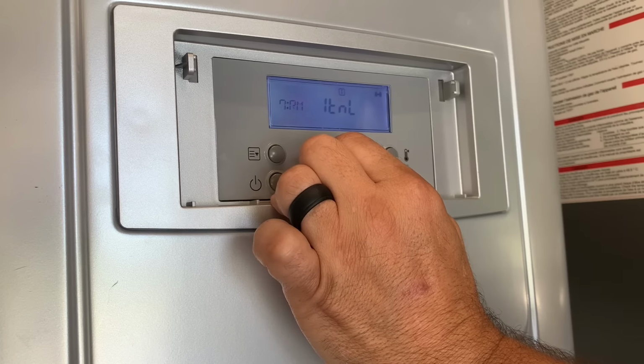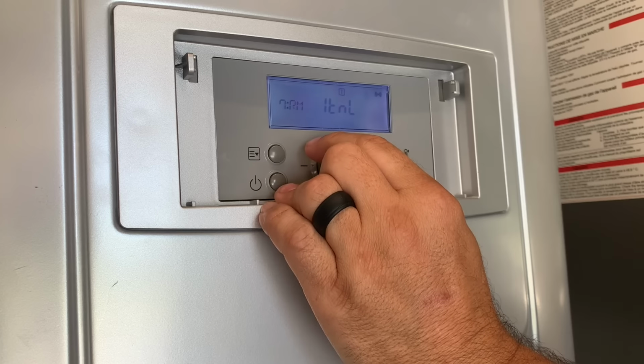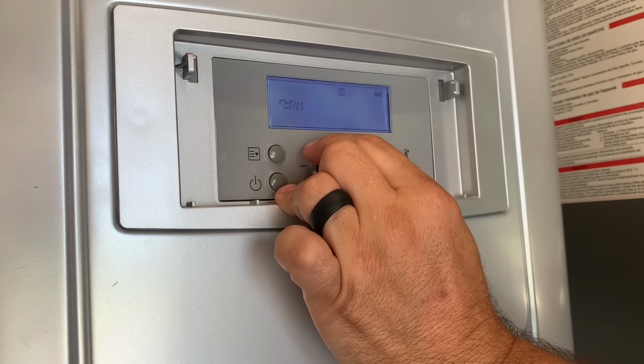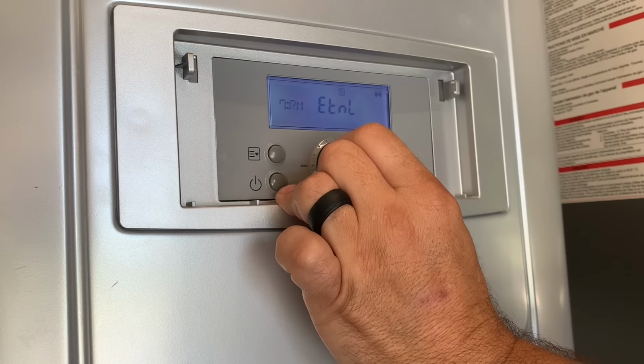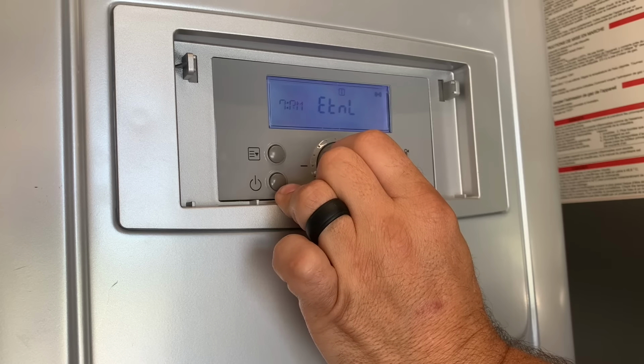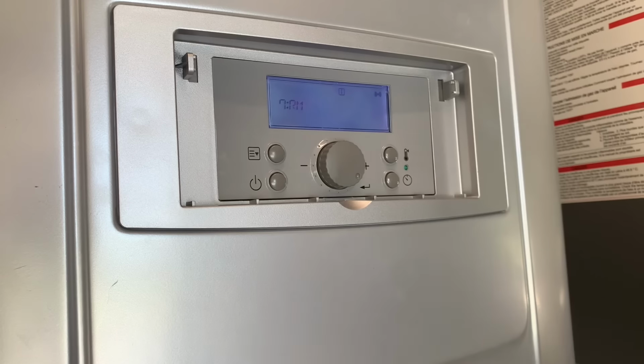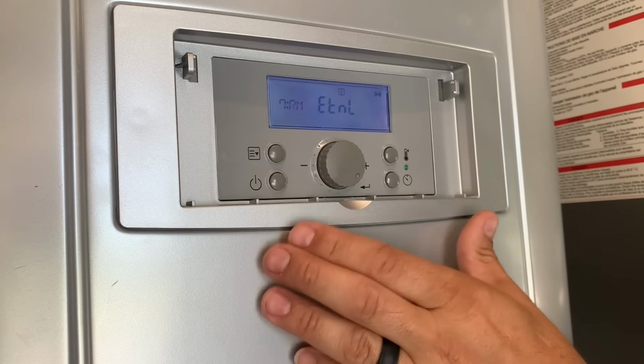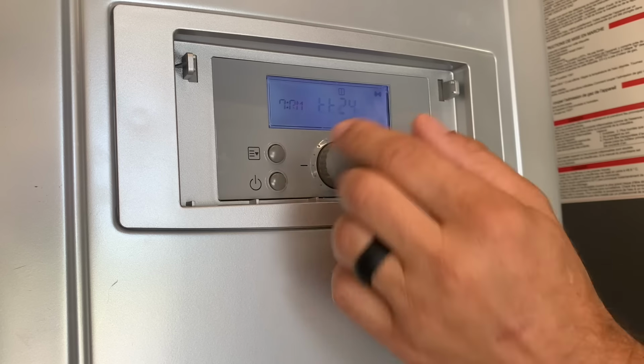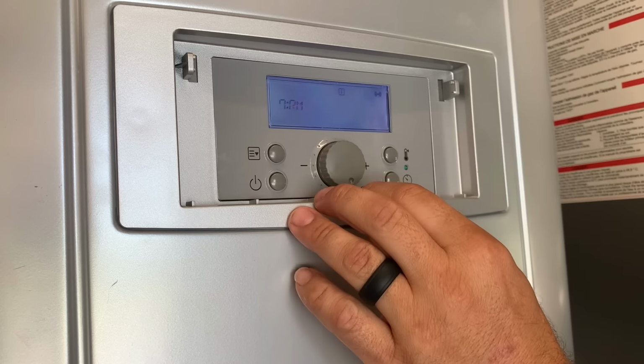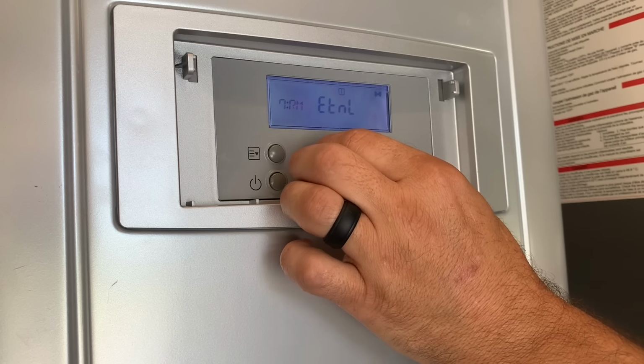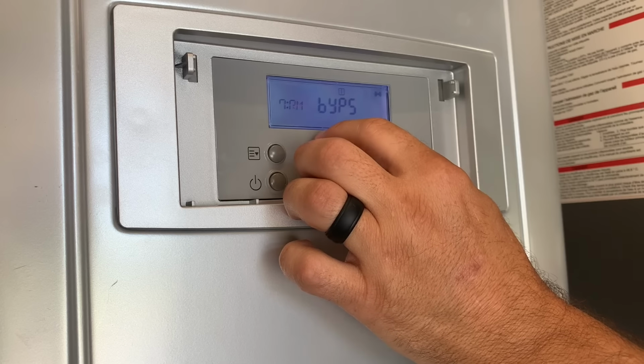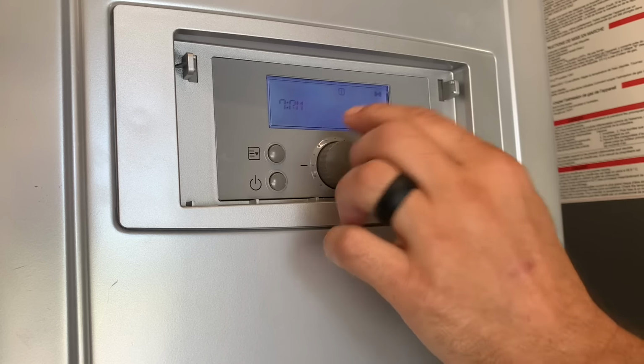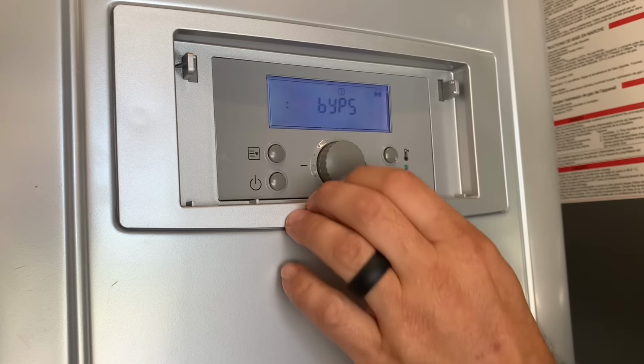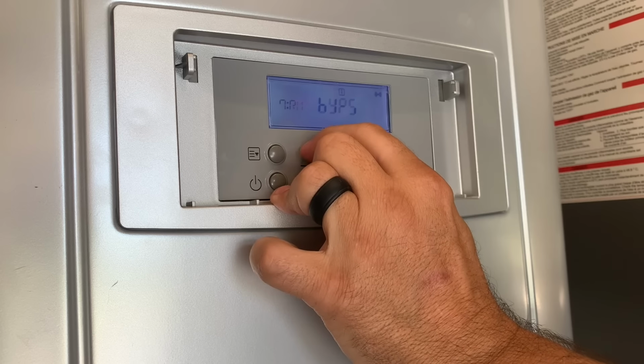So, internal recirculation. This will allow the water heater to recirculate internally, keep it warm, keep the heat exchanger warm. Go down to external. This is external recirculation. This means that you have a dedicated return line and you're going to be circulating through that dedicated return line. Still uses the internal pump. Title 24 and bypass. So you're going to select your application. Now this heater, when we do tests, we use the bypass, so we'll leave it on bypass. All right, moving on from 7RM.